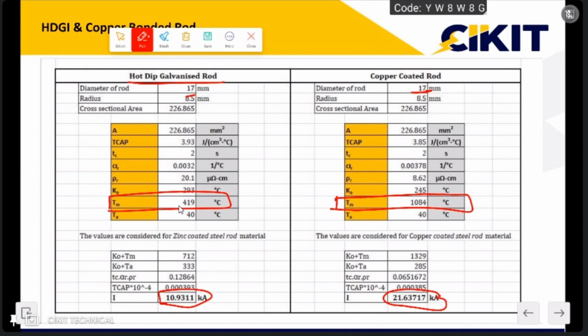So when evaluating these coated materials, we should not evaluate only whether the rod is able to withstand the fault current or not. At the same time, we need to ensure that the rod is able to withstand the fault current without any damage to the coating also. The primary purpose of providing the coating is to protect it from corrosion. If the coating gets peeled off, then the corrosion protection won't be ensured, and hence the material may corrode much faster. So when we are evaluating these coated materials, we need to ensure that the coating is also not damaged during this entire process.